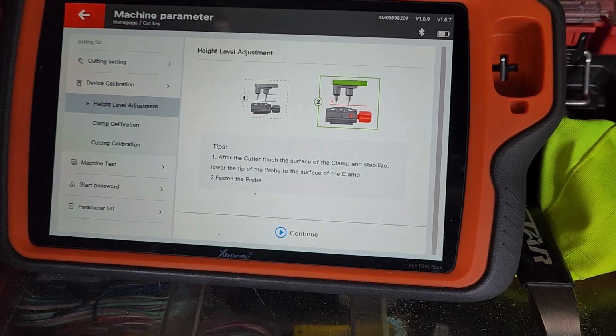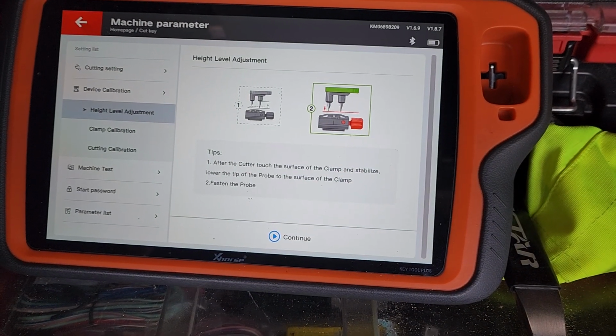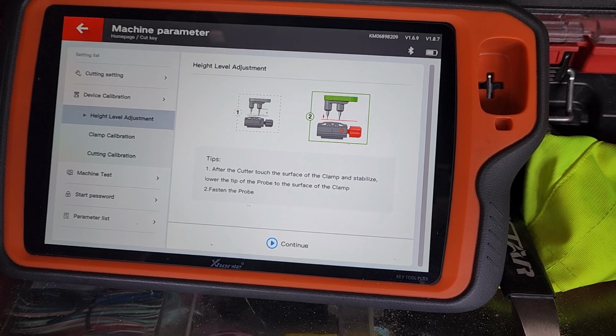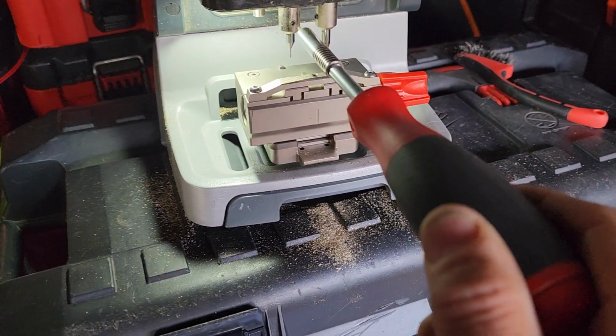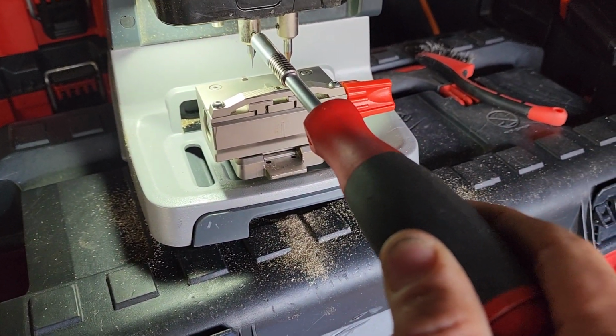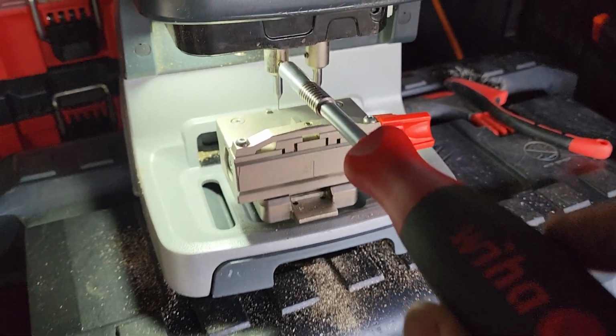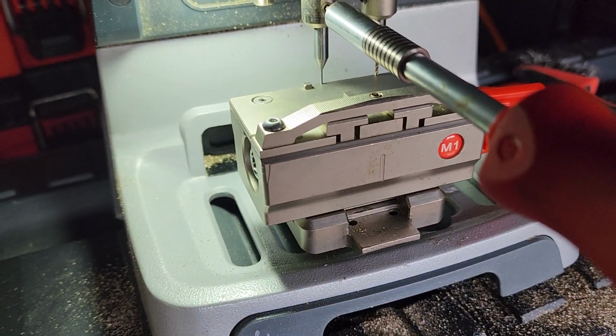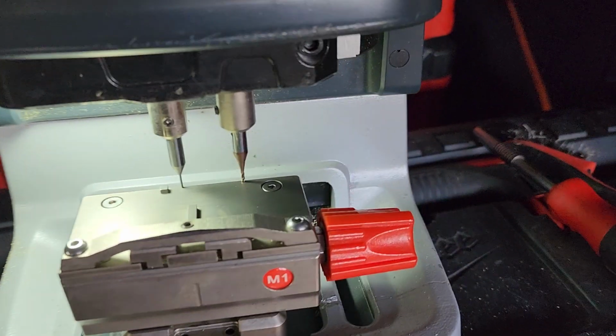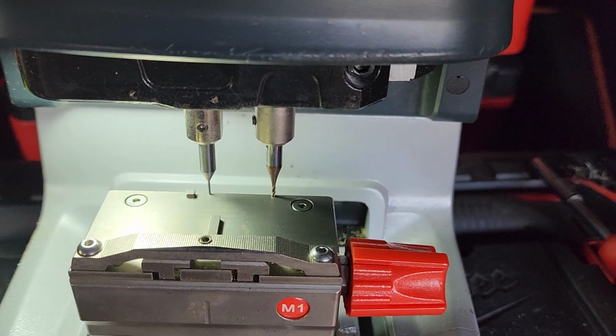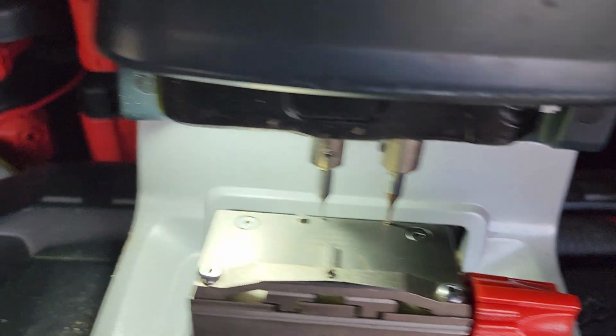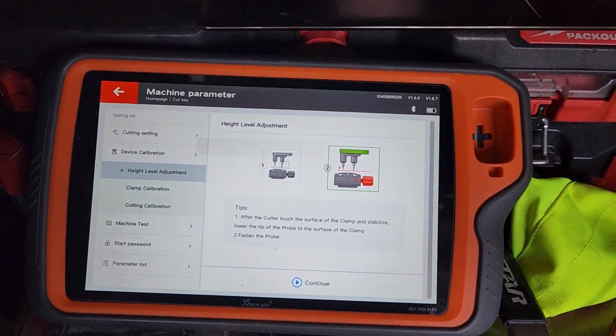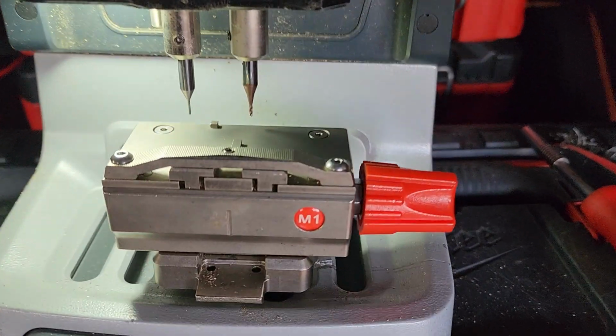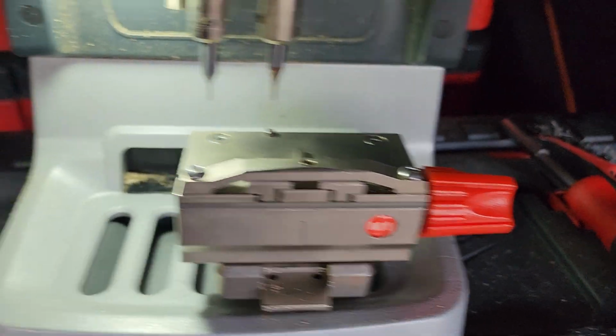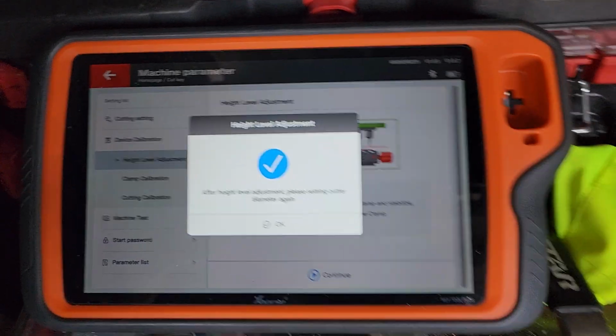This is similar to the M5. Cutter is touching the surface. Lower the tip of the probe to the surface. Let's see if I can do this with one hand. Loosen that up. You saw what it did. It dropped down. What's the reasoning behind this? It now knows that the probe is at the same height as the cutter. Couldn't be anything other. What's it going to do now? It's going to check that height of the probe, height of the cutter, and complete. Of course it wants me to do that.